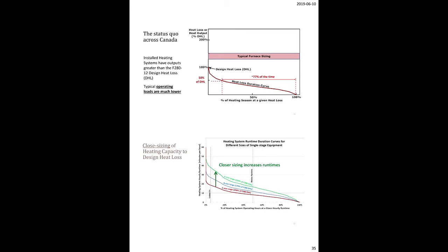I'll give you a sample here. If you really oversize a furnace, I'll use that as an example, air heating, whatever it is, you're going to get a system that's going to run for maybe 10 minutes on average per hour. But if you get closer to right sizing it, you can double the runtime, which is important for delivering the system air. Yeah, two-stage system. It's not just about efficiency, it's about let's get the runtime up. You want to go even further? Go to fully variable. Okay, now, be very careful with this, right?